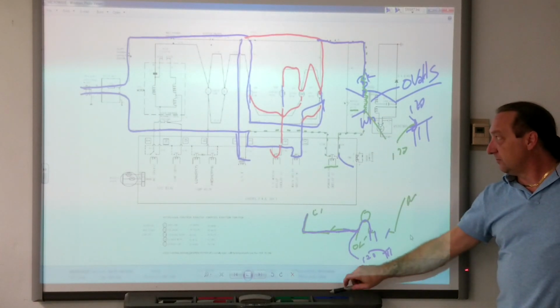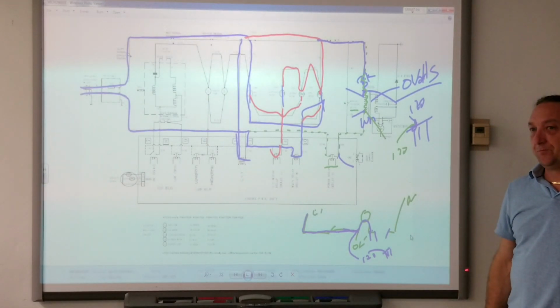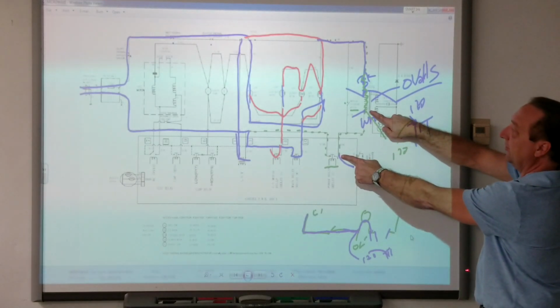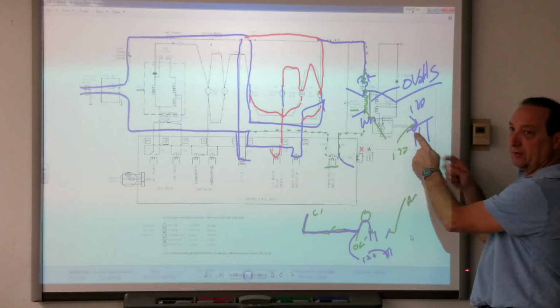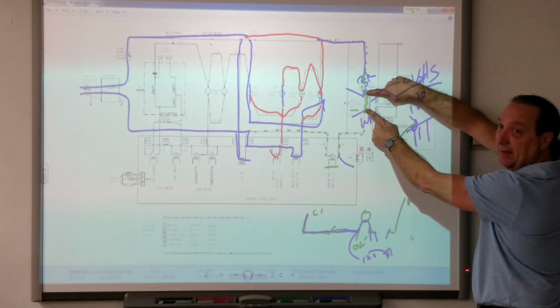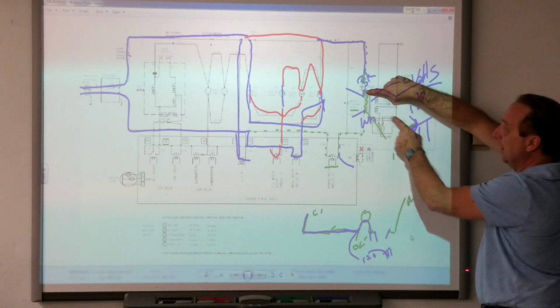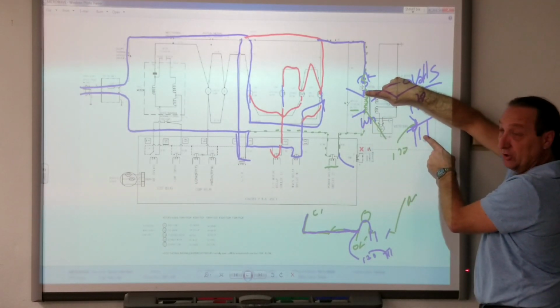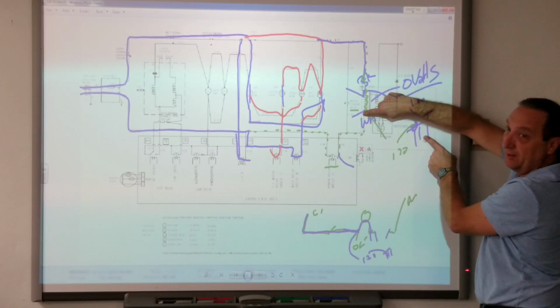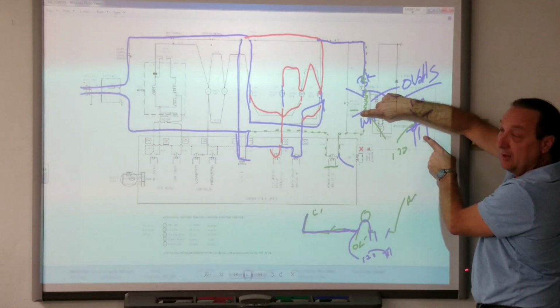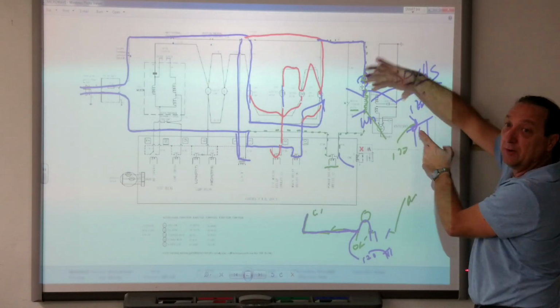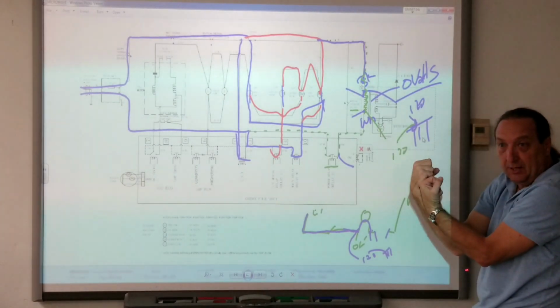Now you said if you check it from the other side of the transformer and the inside of the relay, I don't have both meter leads here, I'm still using ground. I went here and here and I didn't have a voltage reading. Good. I went to ground, I had a voltage reading. I moved this one, I still have a voltage reading to ground. So the only way I have a voltage reading to ground is if the power line is coming in.